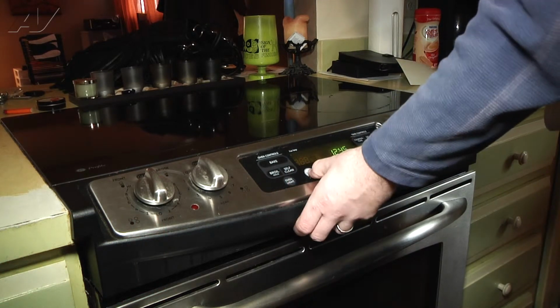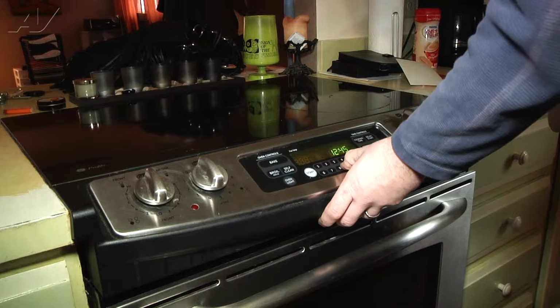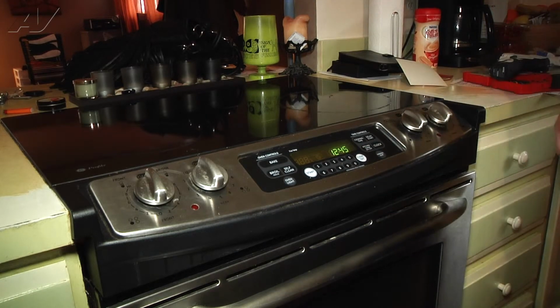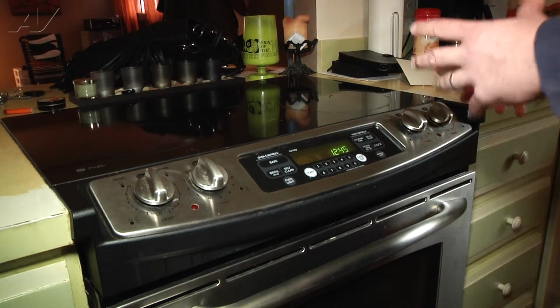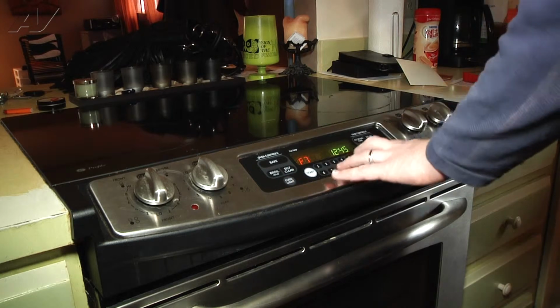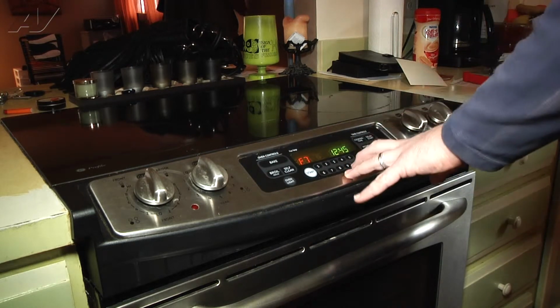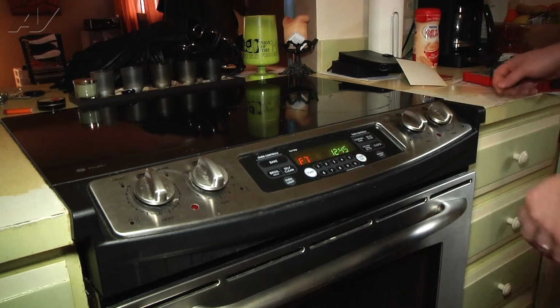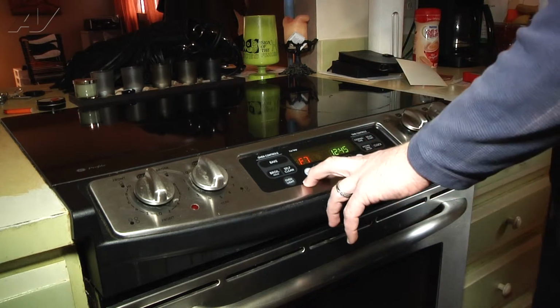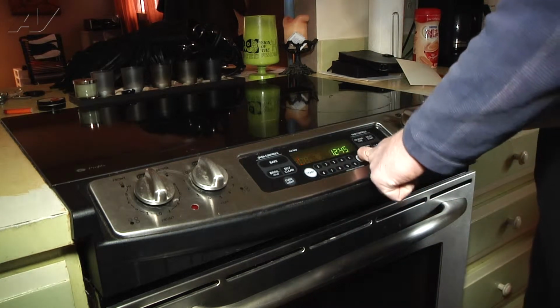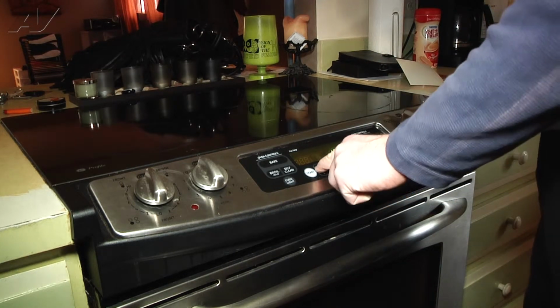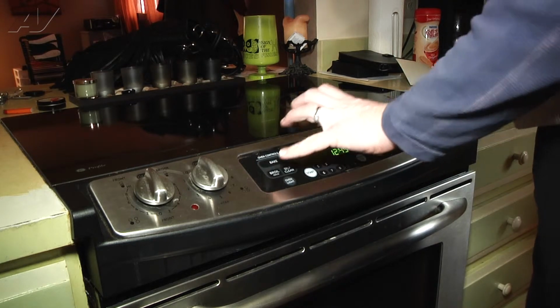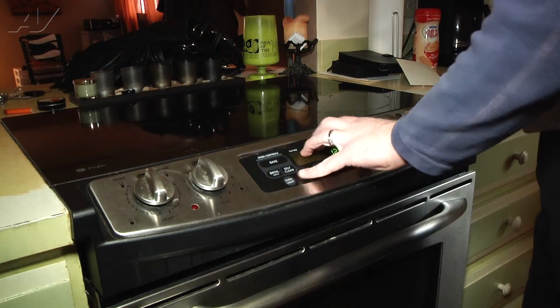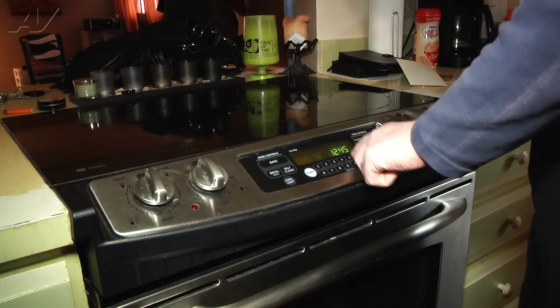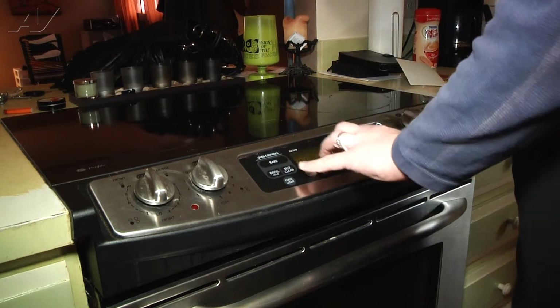The F7 error code is actually an error code for a shorted key on the keypad here, or it could be an issue with the control board itself. We know that most of our buttons are not working, but some of them are, so we do have power coming to our touch panel, but with some buttons not working, we obviously have a shorted or faulty keypad that needs to be replaced.